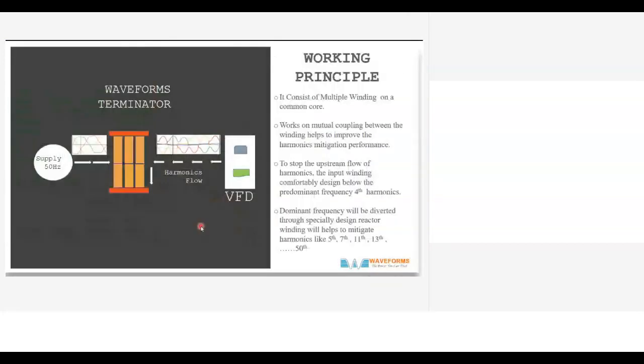the same problem. So this is the working principle of the Terminator, the universal passive harmonic filter. It consists of multiple windings on a common core. So one single structure, with a 3-leg structure, we will have multiple windings. I will tell you why we have multiple. It works on mutual coupling between the windings, which helps to improve the harmonic mitigation performance.